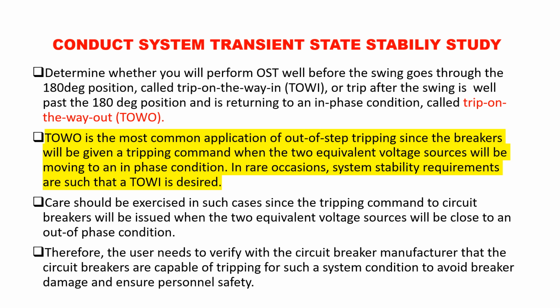It is better to have the out-of-step tripping, that is, isolating the system in islanding mode, when the system is returning and it is not 180 degrees out of phase. Because when it is 180 degrees out of phase, or moving towards 180 degrees out of phase, the breaker duty increases very high, and you must refer to your manufacturer whether you can do this kind of tripping when the power swing is going forward. I mean here that the angle keeps on increasing and moving towards 180 degrees.